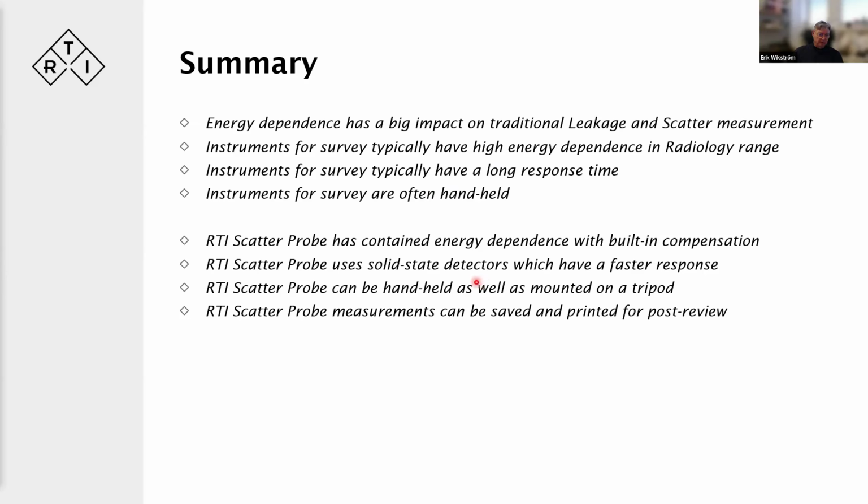So what we offer, and what we've talked about today, is the scatter probe with the compensation for the energy dependence built into the firmware, with the fast response of solid state detectors, mountable on a tripod or handheld.